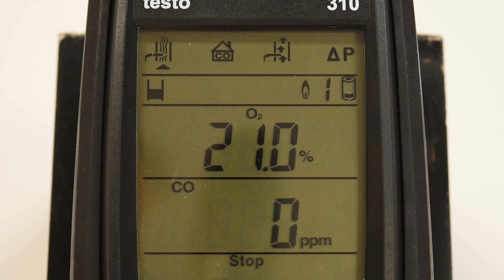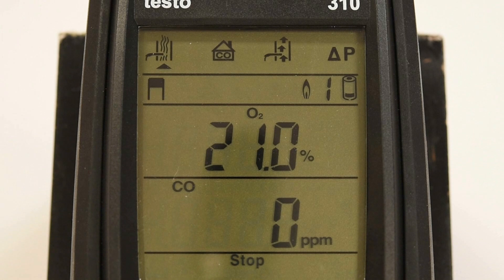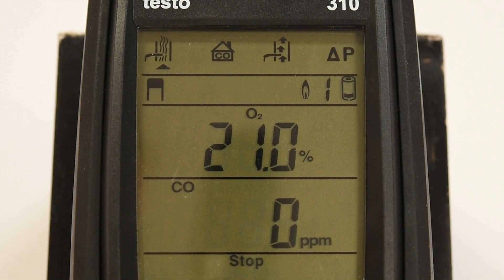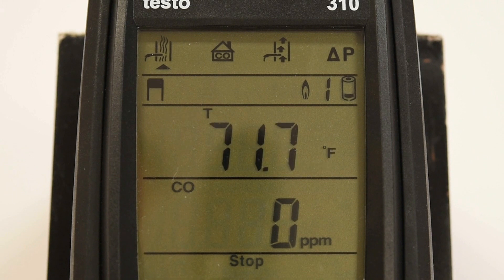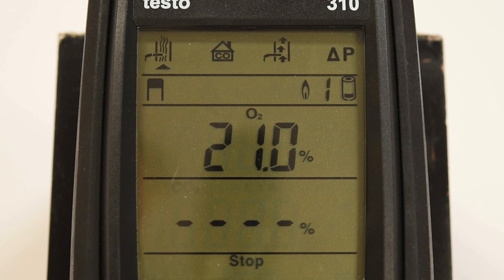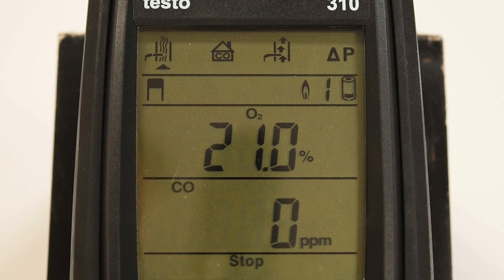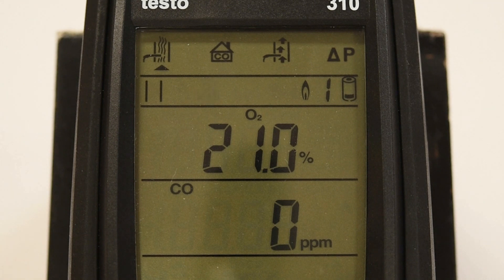When selecting the flue gas test, the measurement values are displayed on two lines. Additional measurement values are calculated simultaneously and can be viewed using the up and down arrows. The up arrow will scroll through the top line's measurements and the down arrow will scroll through the bottom line's measurements. When you are satisfied with your readings, you can send your measurements to the optional Testo IR printer by pressing the print button.